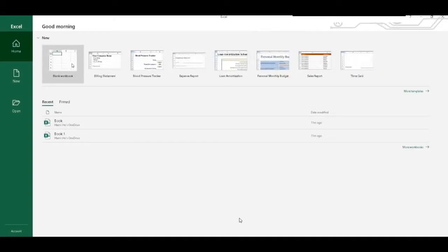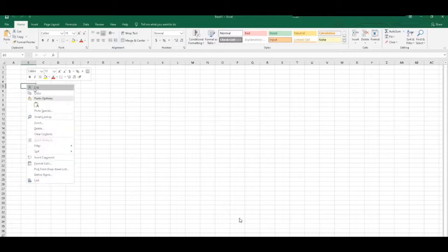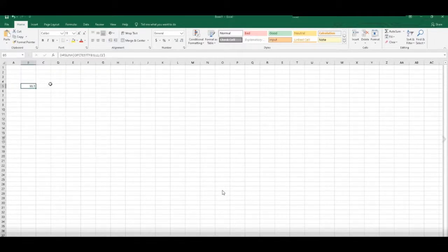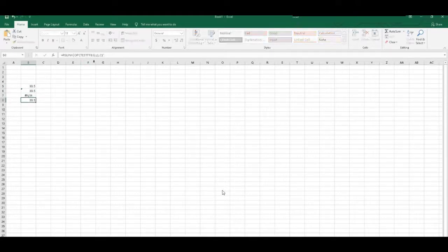We open the Excel and we paste special. Select the paste link and select Unicode Text. Click the OK. Once we paste this link, we will find the actual value from PLC already shown in the Excel. We can drag this link and manually write the next address.